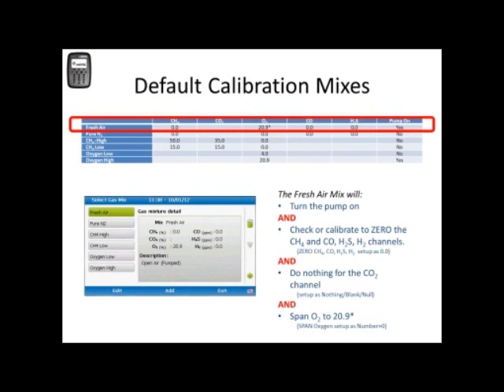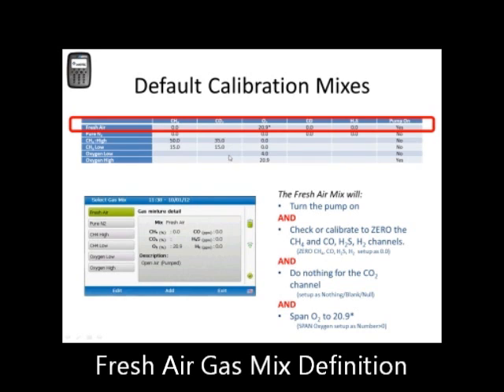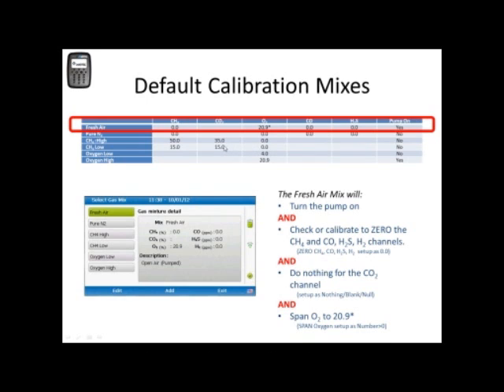So in this gas mix pre-configured from the factory, as you can see, it's a snapshot of just how the 6 gas mixes that we preload from factory are pre-configured, and you can see the values. In this case, we're concentrating on the fresh air. And once again, focus on the fresh air gas mix and keep in mind those 3 basic commands that the GEM5000 recognizes. Under this gas mix, we can clearly see that the mix will check or calibrate the CH4 to 0, do nothing for the CO2, and calibrate the oxygen to 20.9. Okay, in this case, it will also zero the CO and H2S since they have a value of 0.0.